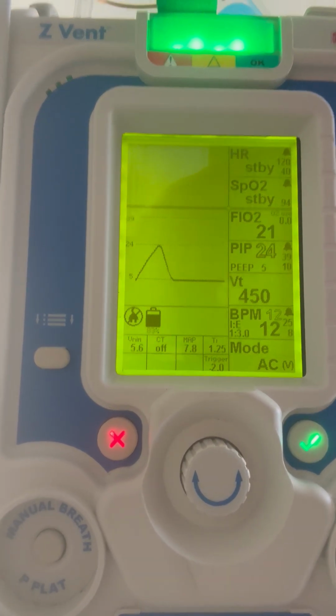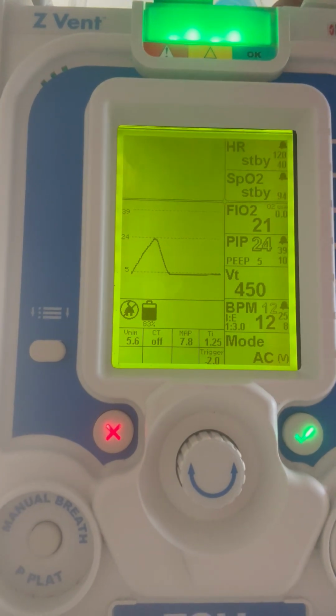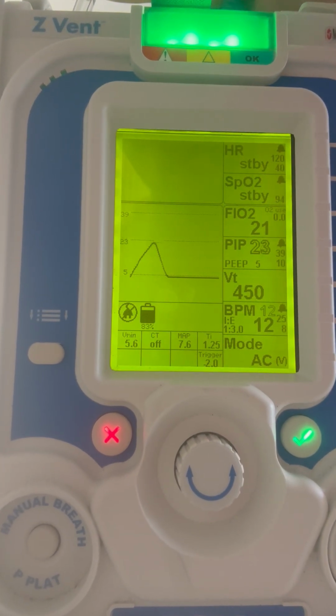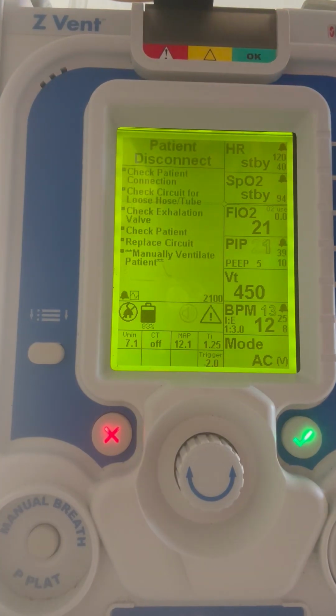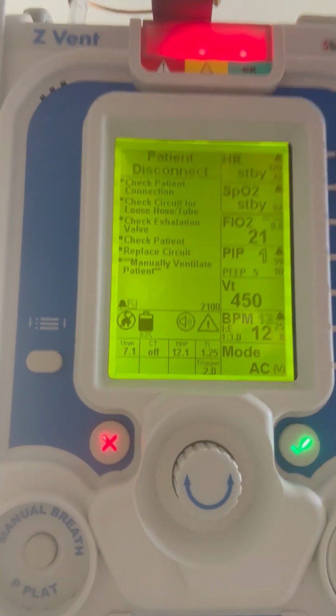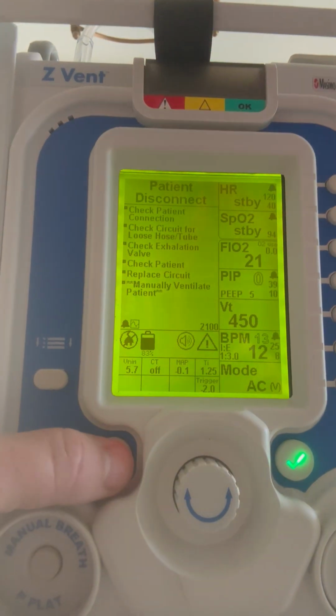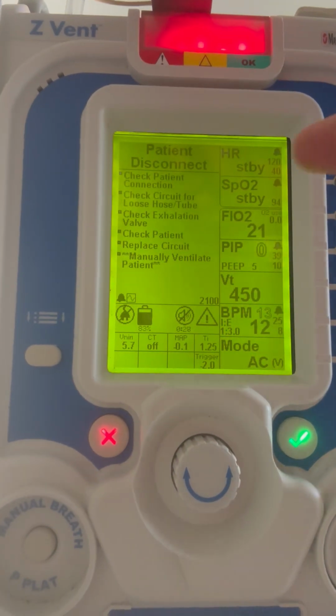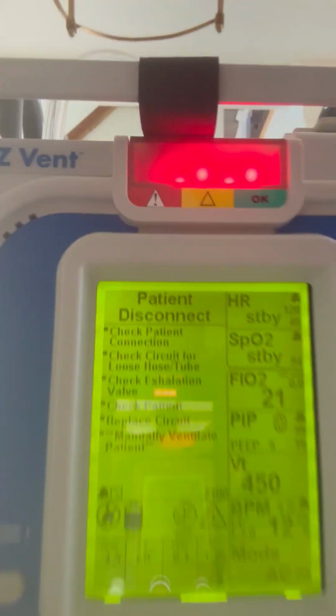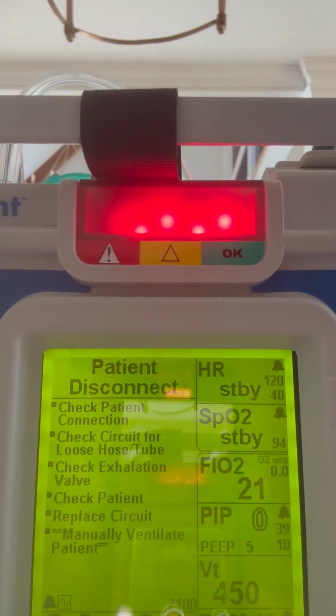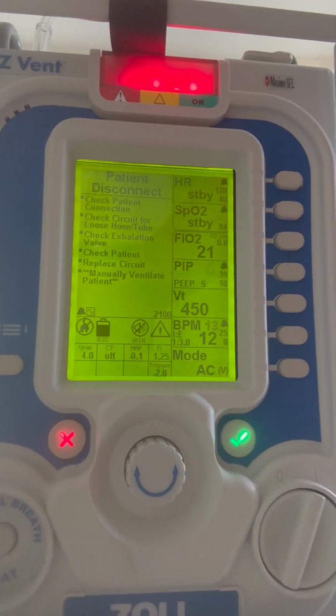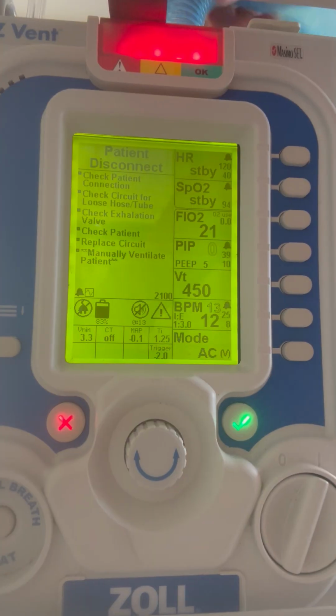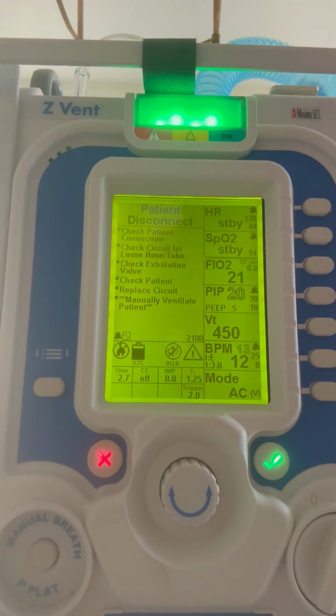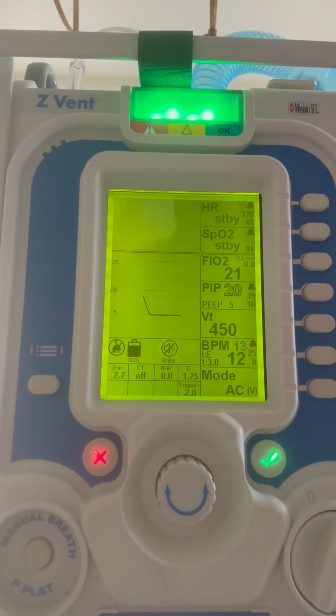One of the things I do want to show you is the alarms. We have Smart Help alarm built into this. So anytime something goes wrong, in this case a patient disconnect, hit the red X to silence it for 30 seconds. It gives you a list of all the things to check for the not as experienced RTs or maybe a tech or someone that's bedside. In this case, simply just a patient disconnect, connect it, one breath, goes back to ventilating.